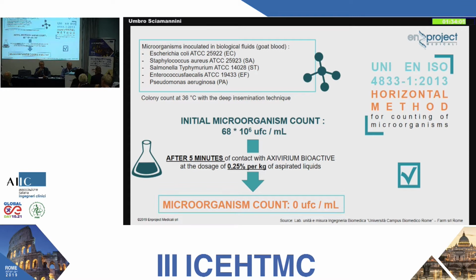5 minutes inside the aspirator, the doctor of the lab took a sample to perform subsequent analysis. The first after 5 minutes, the second after cleaning and rinsing water, the second sample from rinsing water from the exhaust valve and from the suction pipe, because this device performs a thermal disinfection, as you can see later. So we have these 3 samples.